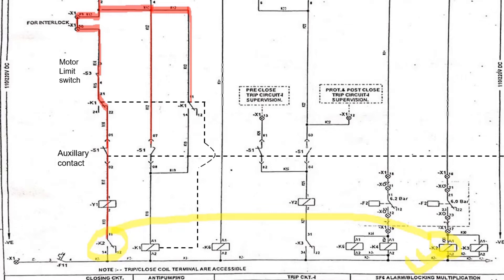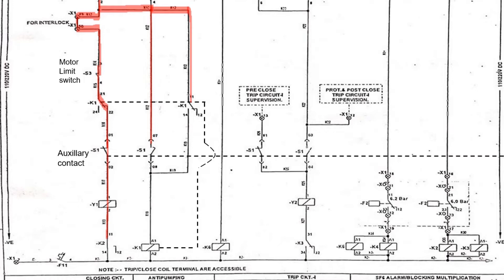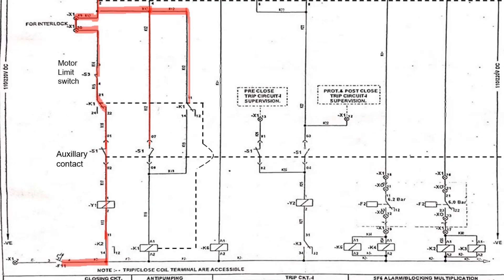K2 contact will get closed only when the gas pressure in the circuit breaker is greater than 6 bar. When the gas pressure is greater than 6 bar, the K2 coil is energized and it changes its contacts — NO becomes NC — and the current will flow through K2. The current will stop at the fuse if the fuse is melted or not in service condition, and will flow through it only when the fuse is kept in healthy condition and in service position.